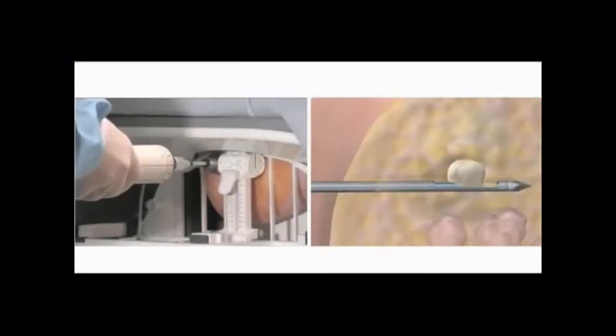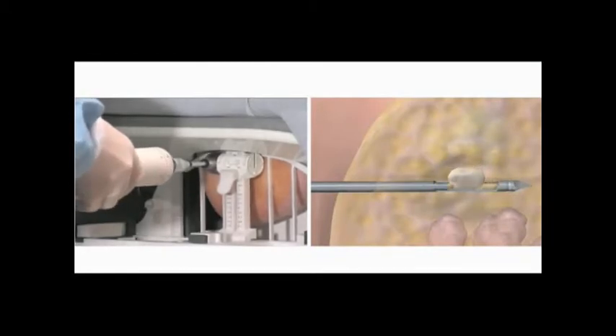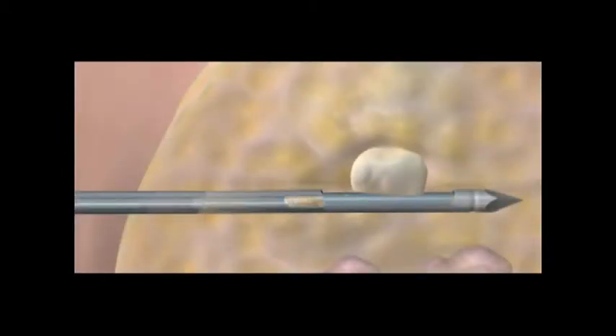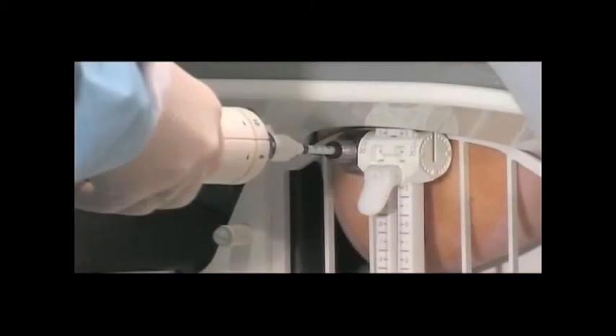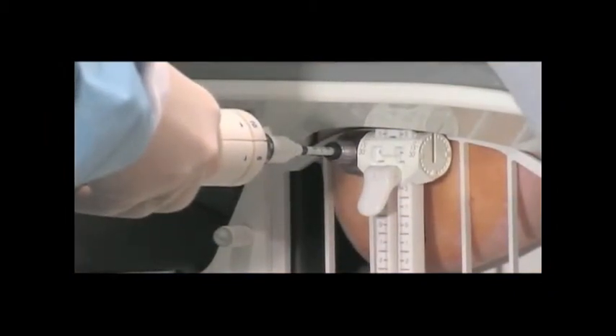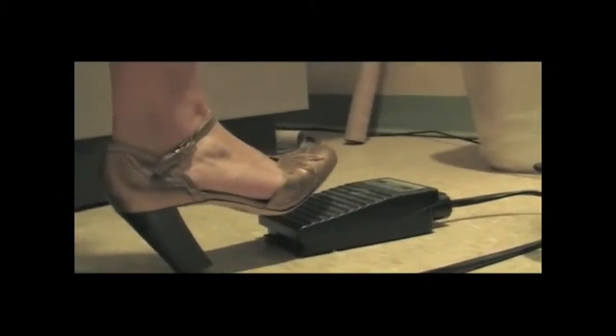Depress the foot switch to activate the biopsy system and continue to hold the foot switch down throughout the tissue acquisition sequence. Tissue acquisition occurs every 4.5 seconds. A beep indicates the end of one cutting cycle. Manual rotation of the handpiece occurs just after the beep during the resting phase of the biopsy cycle. The ATEC handpiece acquires tissue samples until the foot switch is released and all necessary core samples have been retrieved.